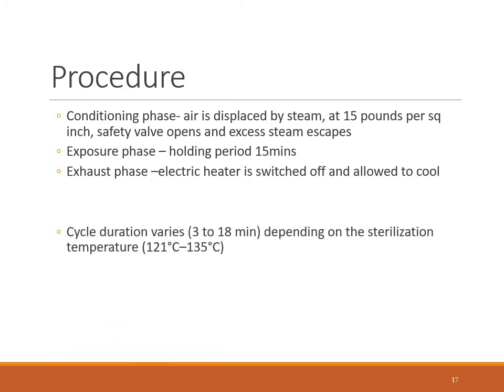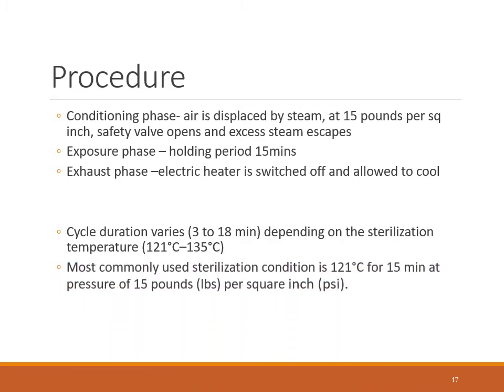The cycle duration varies from 3 to 18 minutes according to the material which we are going to sterilize, and depends on the sterilization temperature. The most commonly used sterilization condition is 121 degrees Celsius for 15 minutes at a pressure of 15 pounds per square inch.